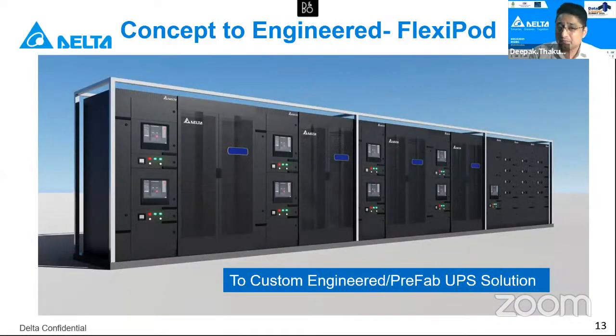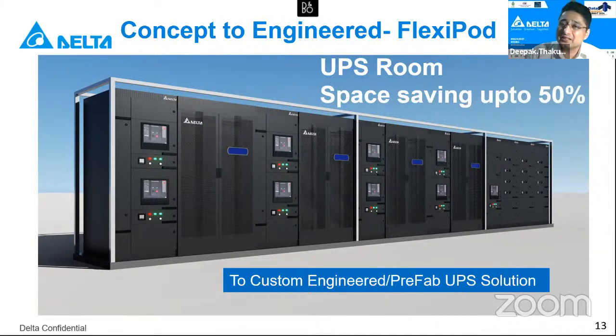And then we create a custom engineered prefab UPS solution from standard components, which are proven and tested by the original UPS architectures. Now, how does it help? Like I said, 50% space saving. It also reduces the duplication of many switchgears within the UPS room. Too many duplications happen because your electrical panel vendor is providing something and your UPS vendor is also providing standard switchgears which are not required at all and never utilized in their lifetime.